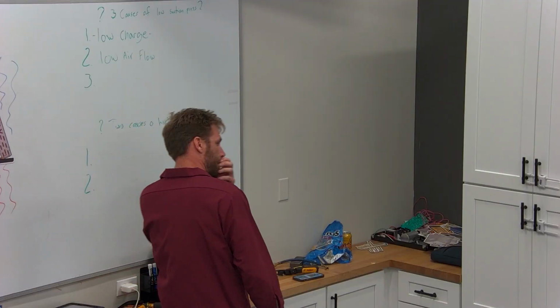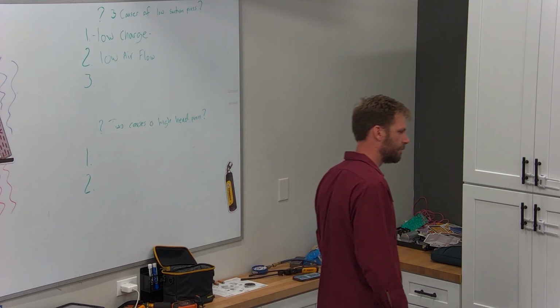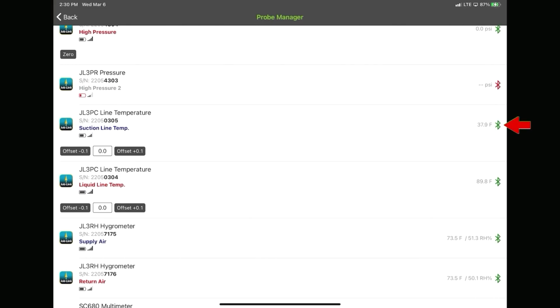Can we see the suction line temperature, 48 degrees? Alright, watch this. What's happening to my suction temperature? Drop it. Whoa, what are we at now? Yeah, 38. What'd I do? You took it, added more air. No? Less pressure, I mean, because it's open. More space. We did not add more air to the coil though. This didn't increase the heat load.